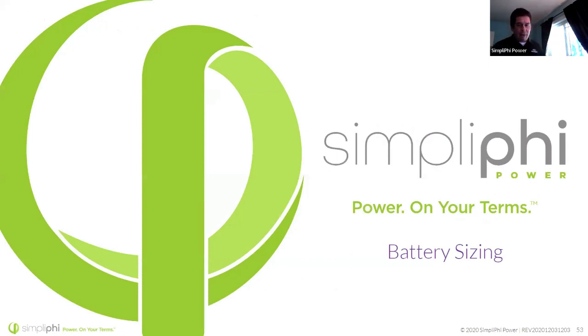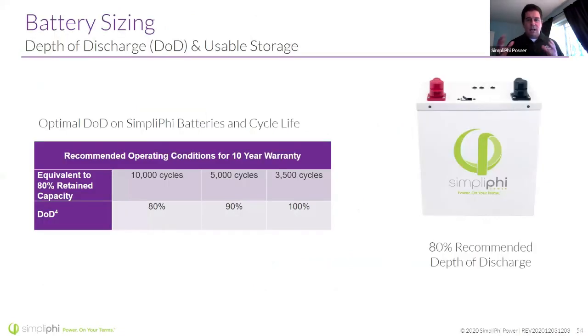We're going to talk a little bit about battery sizing. We talked about depth of discharge. When we say 80% depth of discharge, we are anticipating 10,000 cycles. So again, if you take this battery down to 100% every day, you're still going to get 10 years of use out of it. And we still anticipate 80% of nameplate at year 10. But if you take this thing down to 80%, not only going to get year 10, you're probably going to get another 10 and then maybe half again out of this battery. So your life of the battery is greatly extended by reducing your depth of discharge by just 20%.